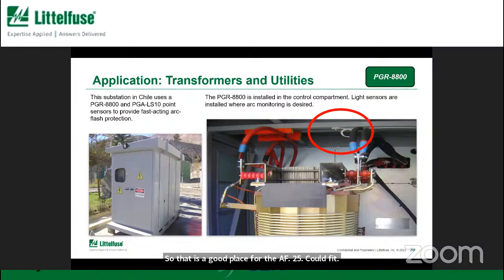Another common application is in some of the transformer compartments. This in particular was a medium voltage utility transformer in South America. And here we see one of those point sensors installed at the top of the cabinet, so it is very easily able to see any arcs across those terminals on the top of the transformer.